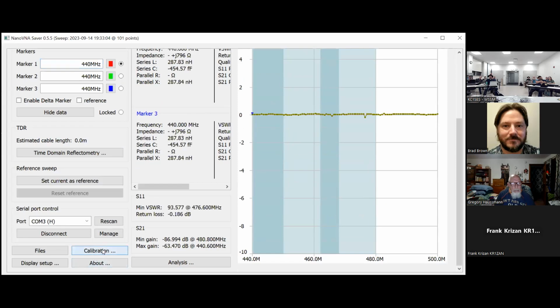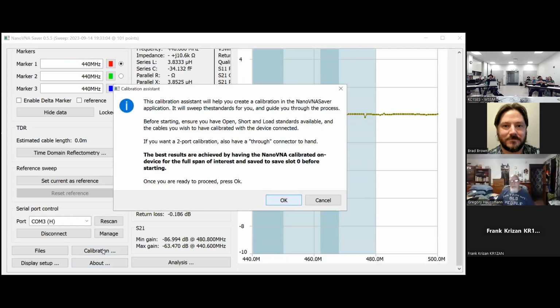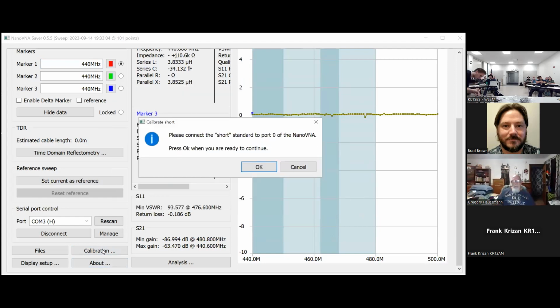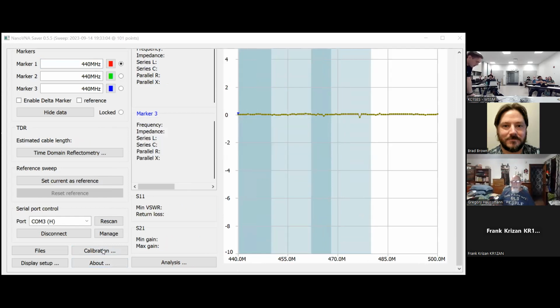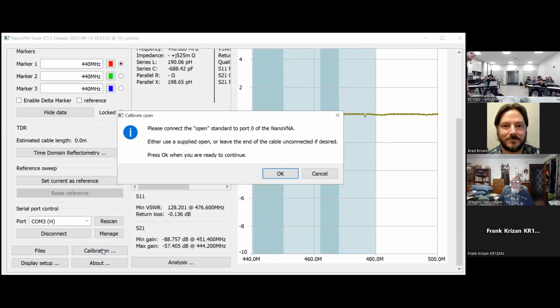All right, now I'll come down, calibration assistant, hit OK. And it's going to say, please connect the short. So let me grab the short standard, plug that in, and make sure you're not touching this because you will interfere with it. I'm going to hit OK and it's going to do the calibration. If you notice, it says 101 points. That is because I only set one segment to sweep. If I had set 10 segments to sweep, it would show me 1010.